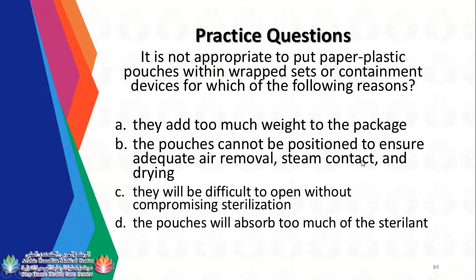Okay, not the pouch. Because sometimes, when you are using a rigid container and there is a pouch inside, the steam or puddles of water will remain on the plastic side of the pouch. So it is not appropriate to put paper plastic pouches within wrap sets or containment devices, because the pouches cannot be positioned to ensure adequate air removal, steam contact, and drying.